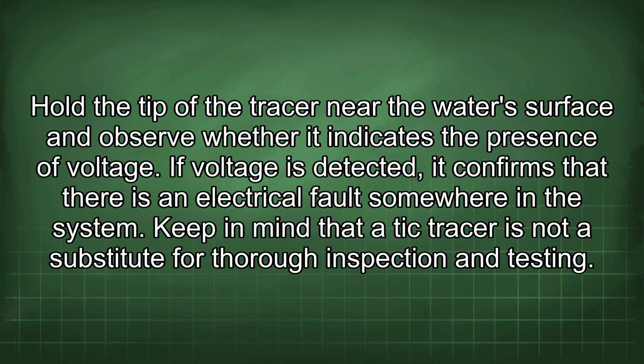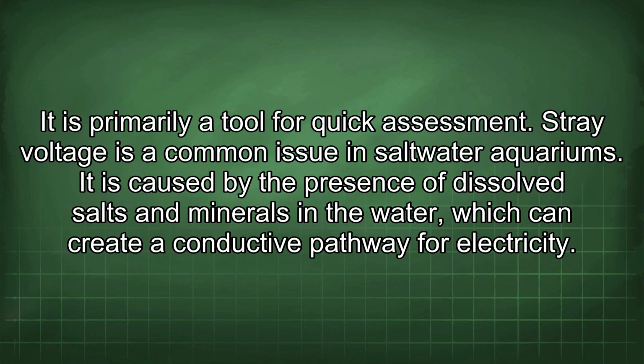Hold the tip of the tracer near the water surface and observe whether it indicates the presence of voltage. If voltage is detected, it confirms that there is an electrical fault somewhere in the system. Keep in mind that a tick tracer is not a substitute for thorough inspection and testing. It is primarily a tool for quick assessment.